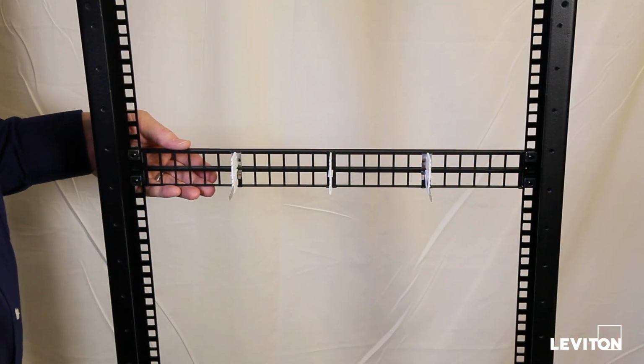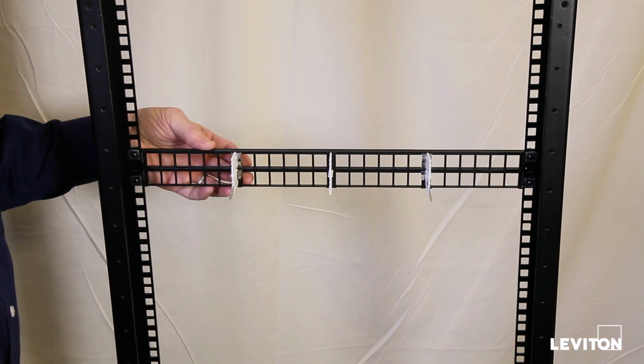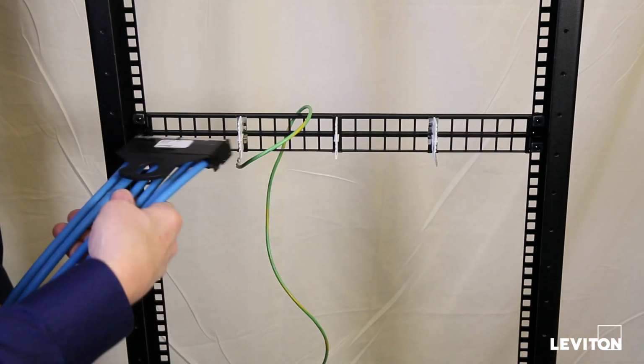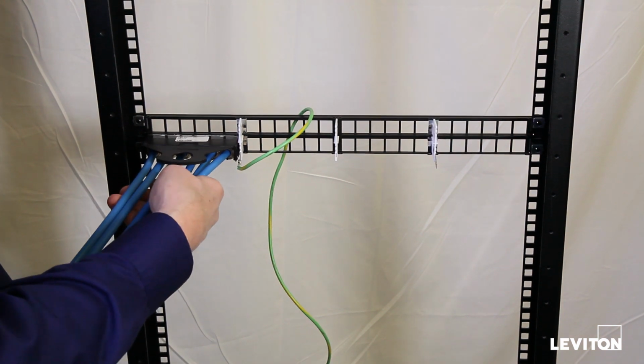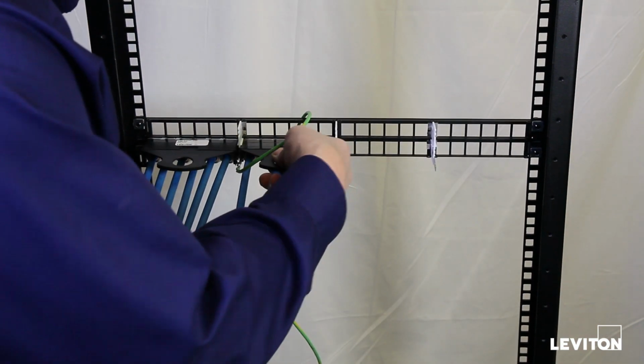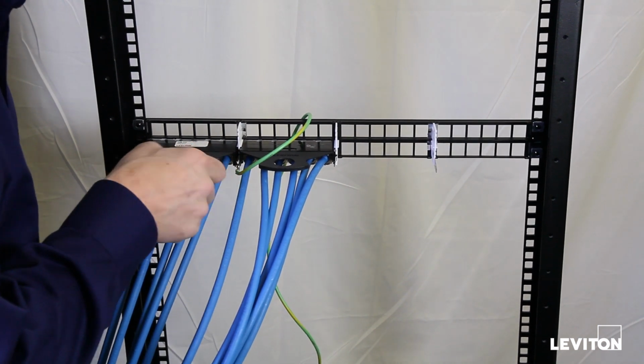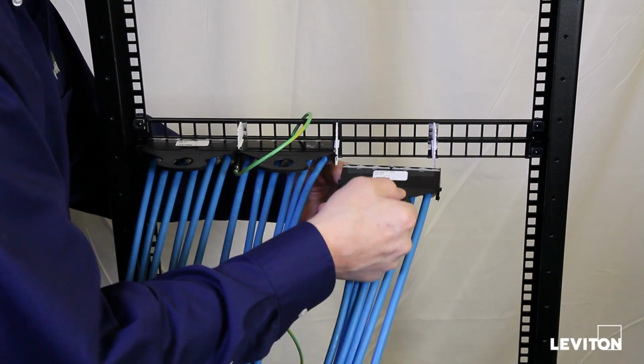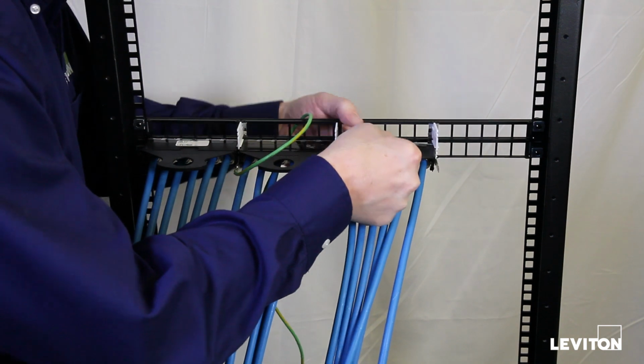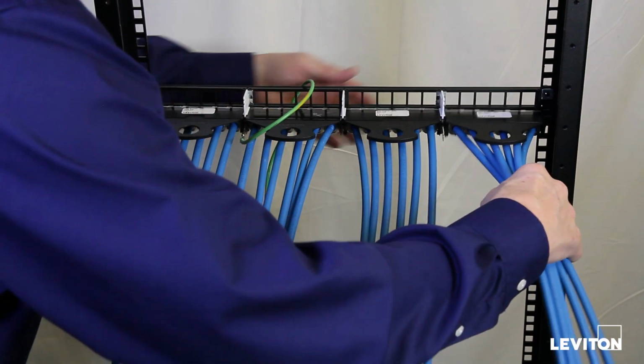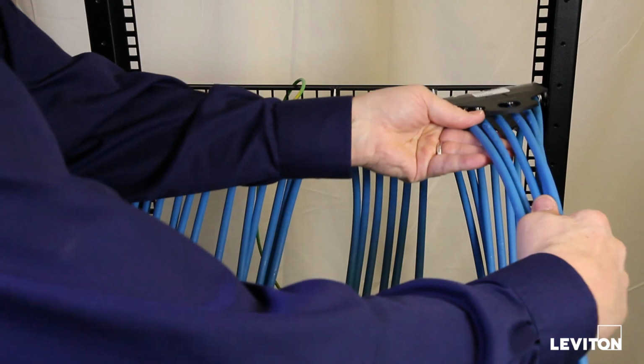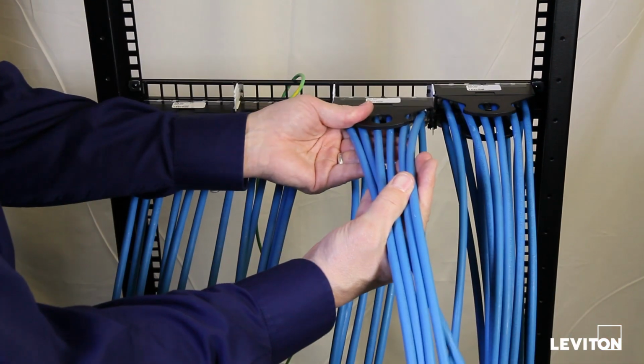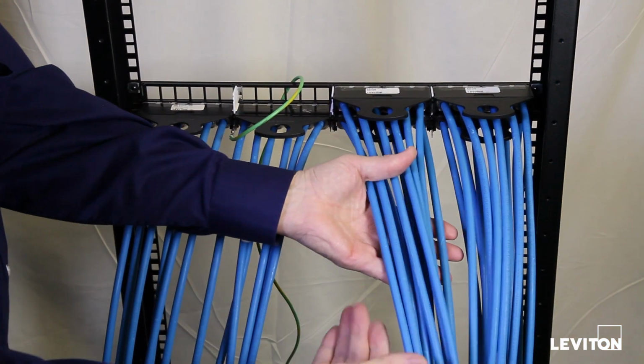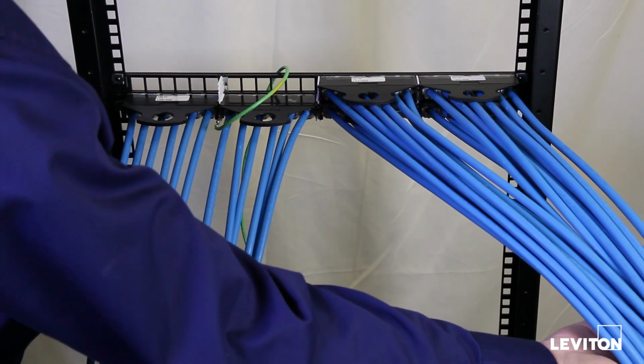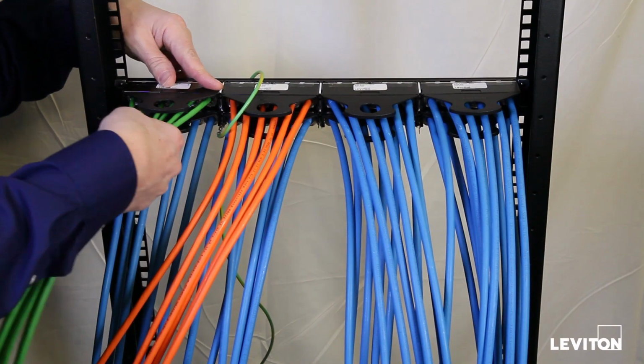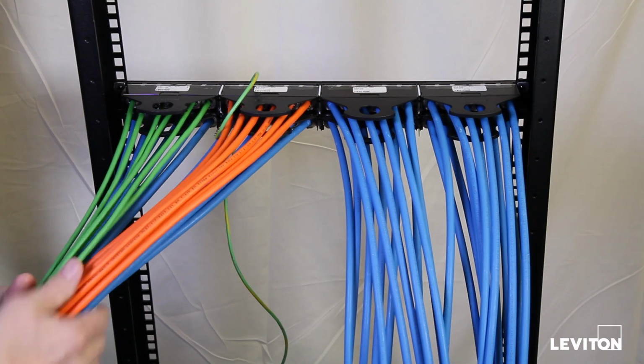Now we will demonstrate how to load the flat panel with cable coming from a raised floor. Start by routing the cables from the left side of the rack. Insert the cassettes into the bottom row, starting with the port at the left edge of the panel and working toward the center. Then route the cables coming from the right side of the rack, starting with the port at the center and working toward the right edge of the panel. Load the top row in the same manner, this time starting at the right-hand side and working toward the center. Dress the cables from the right to the right. Dress the cables from the left to the left.